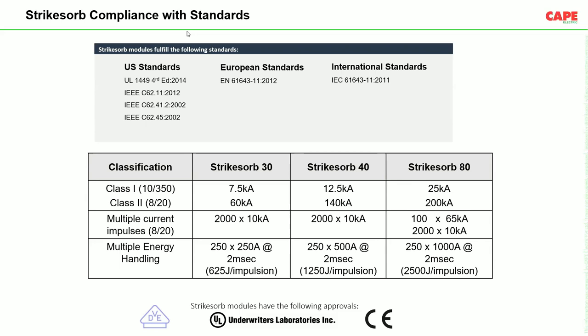So aluminium acts like a heat sink for the MOV. As soon as the MOV is hot, it is cooled down quite a bit faster in comparison to a dendrite SPD. And that is the reason these SPDs are able to withstand multiple strikes. You can see the last one: Strikesorb 80, 100 times 65 kA, 2000 times 10 kA. And after that, multiple high energy handling.